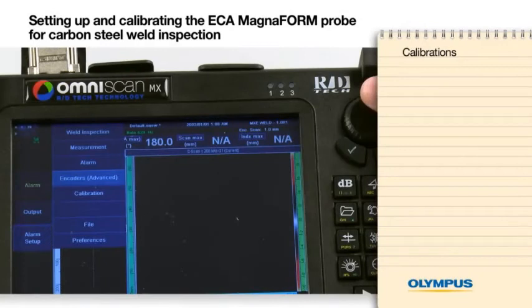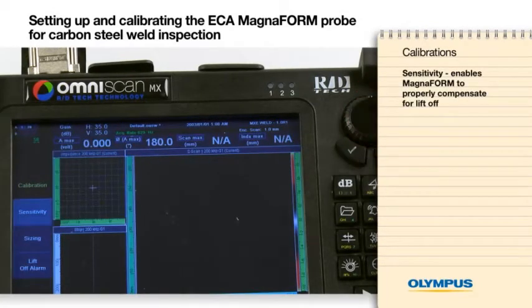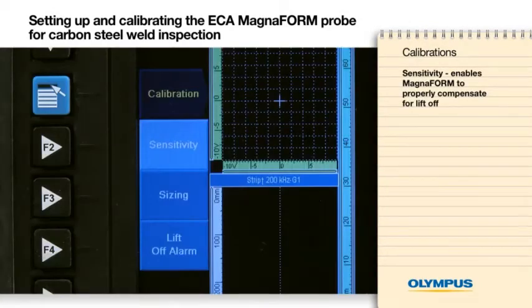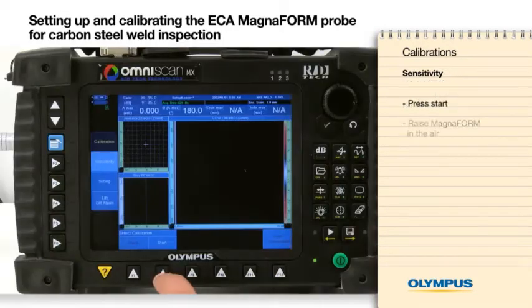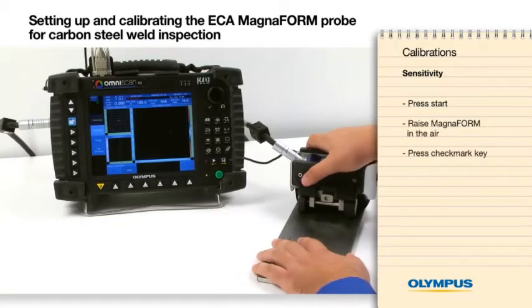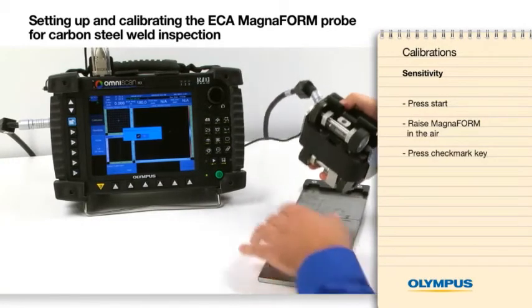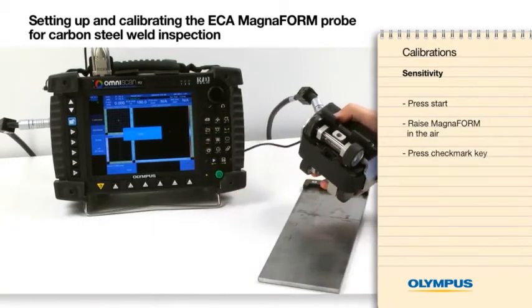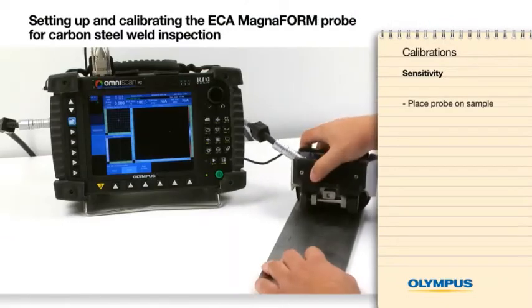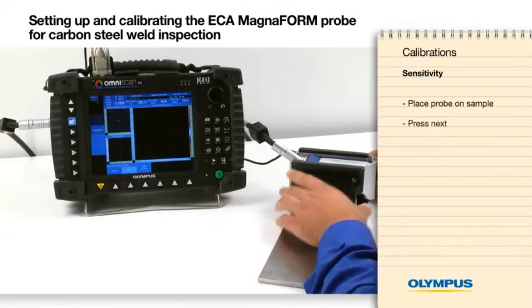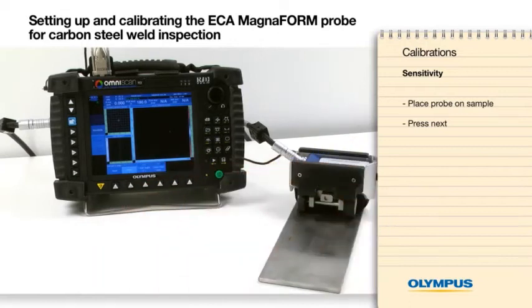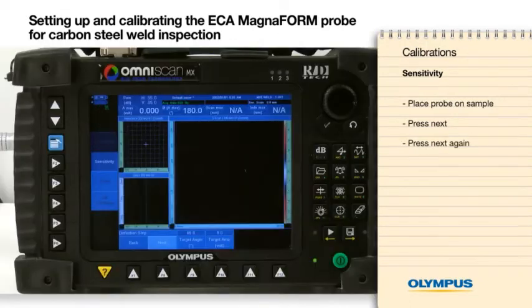The first calibration to be done is a sensitivity calibration. Sensitivity enables the MagnaFORM to properly compensate for liftoff. Press start and raise the MagnaFORM in the air and press the checkmark key. Place the probe on the carbon steel calibration sample and press next. The default settings are correct for this type of material. Press next again. Press start and scan the full notch.